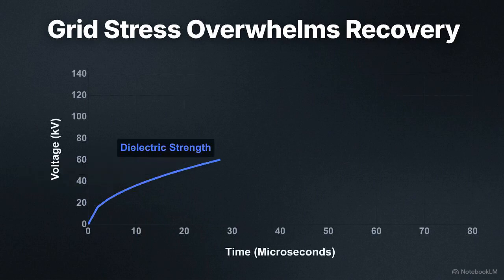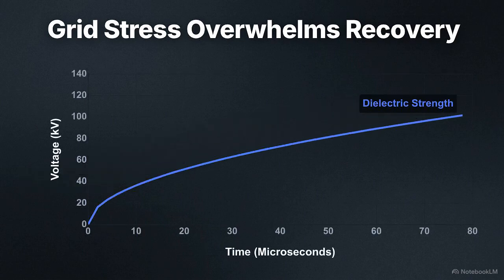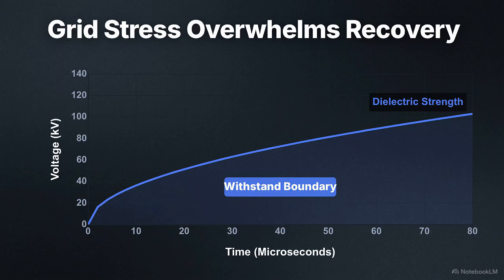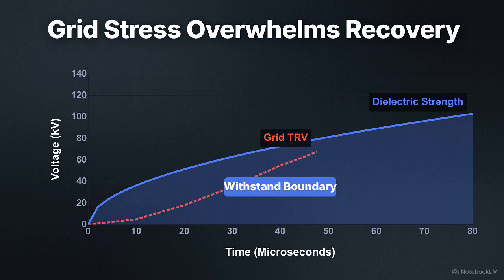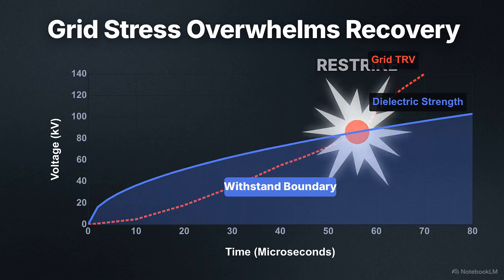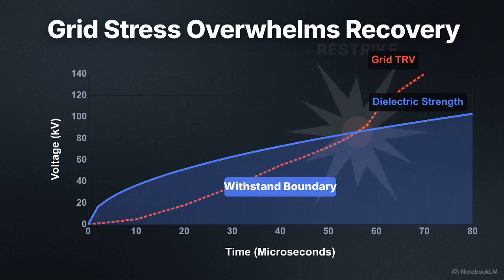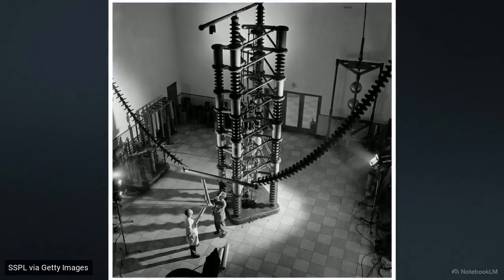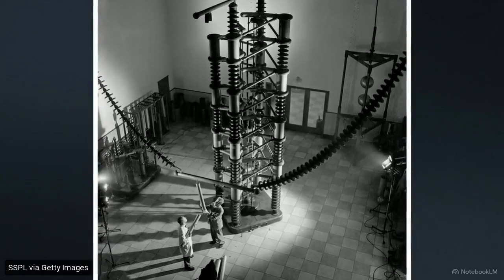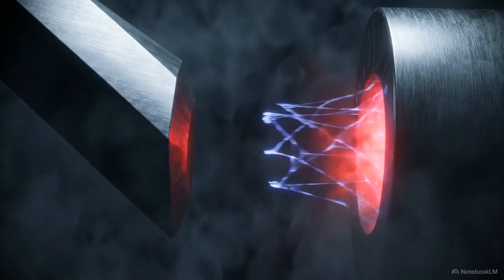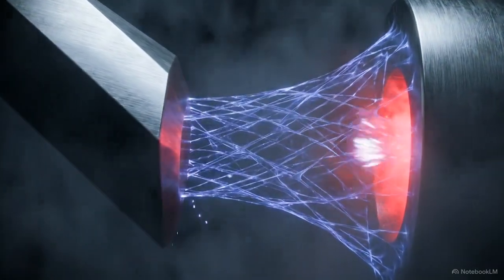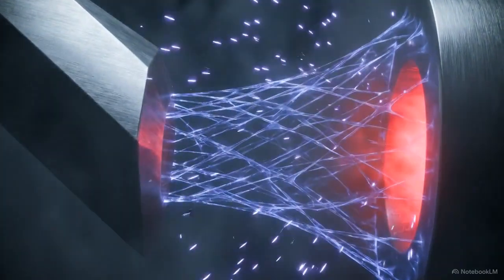We can plot this on a graph. This upward curve is the breaker's dielectric strength over a microsecond timeline, creating a hard withstand boundary. This second line is the grid's TRV. If it pierces the boundary before the breaker recovers, we get a restrike. High voltage capacity alone isn't enough to survive. The breaker must have the raw speed to rebuild its internal insulation faster than the grid can apply the stress.